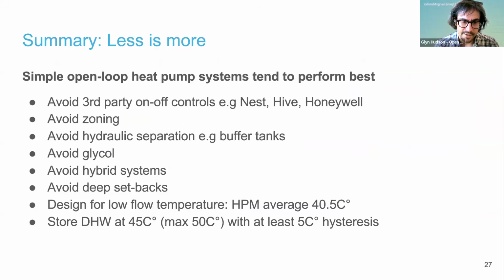So in summary, these are the main things that we've found to improve or avoid poor performance of heat pumps. So in general, simple open loop heat pump systems tend to perform best. Avoid third-party controls. Best to use the inbuilt heat pump controls where possible. Avoid zoning, avoid buffer tanks, hydraulic separation, avoid glycol, avoid hybrid systems, avoid deep setbacks in the schedule.